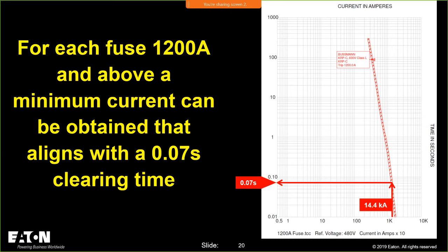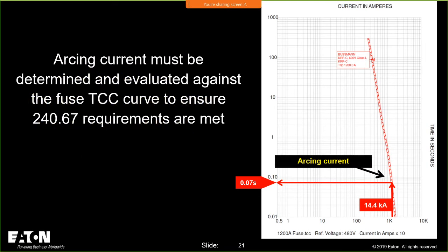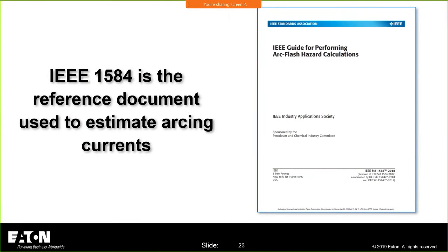seconds. And what I'm doing there is basically plotting the arcing current, the lowest arcing current, if you're going to do things, in my opinion, the right way. You're going to display or plot the lowest arcing current and establish a 0.07 second clearing time. And I know arcing current is not a term that's in the NEC right now. It's not defined anywhere in the NEC, but it is defined in IEEE 1584, and it is calculated in IEEE 1584. And what I'm showing you here is the 2018 version. So we have the latest version of IEEE 1584 that we're looking at.